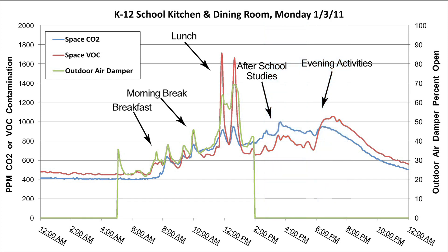Whether it's children or adults in the room, and whether they're studying or eating, the chart shows that the VOC sensor output directly correlates to occupancy in the area. The chart also shows that using the VOC sensor to control the outdoor air damper results in appropriate ventilation for the space.